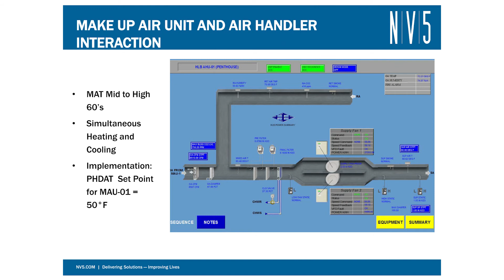The next example that we have is kind of a trivial one. I mean, everybody has seen an air terminal unit that's driving an entire unit. What we saw here was a space that had changed purpose. This wasn't intended to be an IT or control room, but it became that, and the box that was in there couldn't maintain that colder set point. We recommended that they remove it from the static pressure reset program as the short-term solution, and that they install a fan coil unit dedicated to that space, as that is what the university typically likes to do with those spaces.